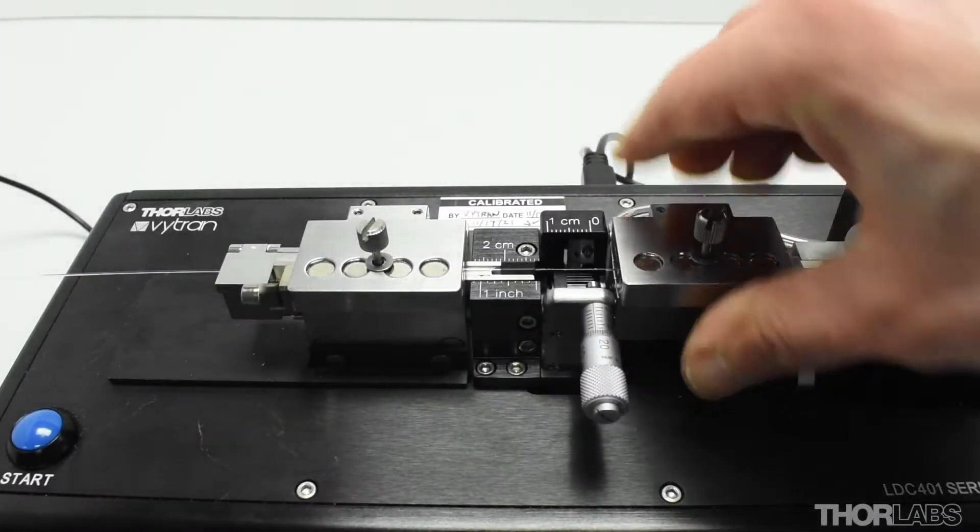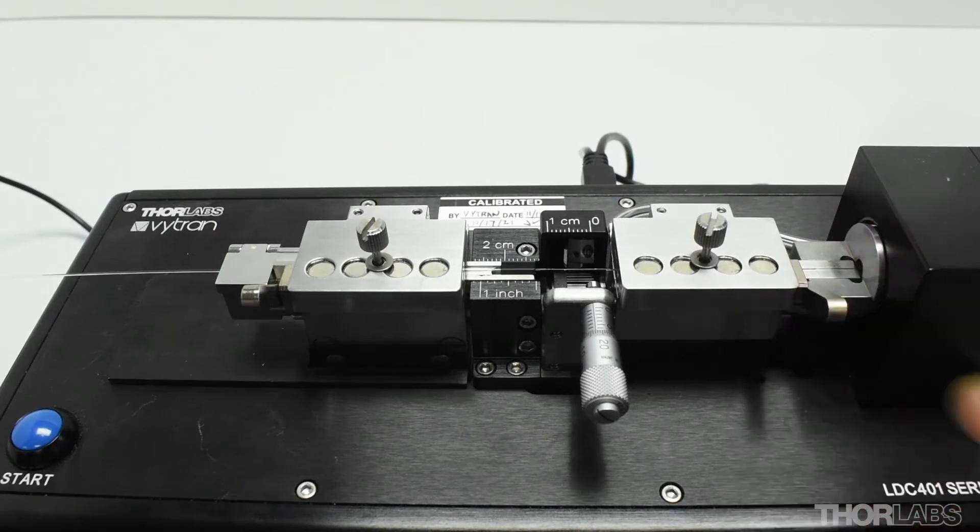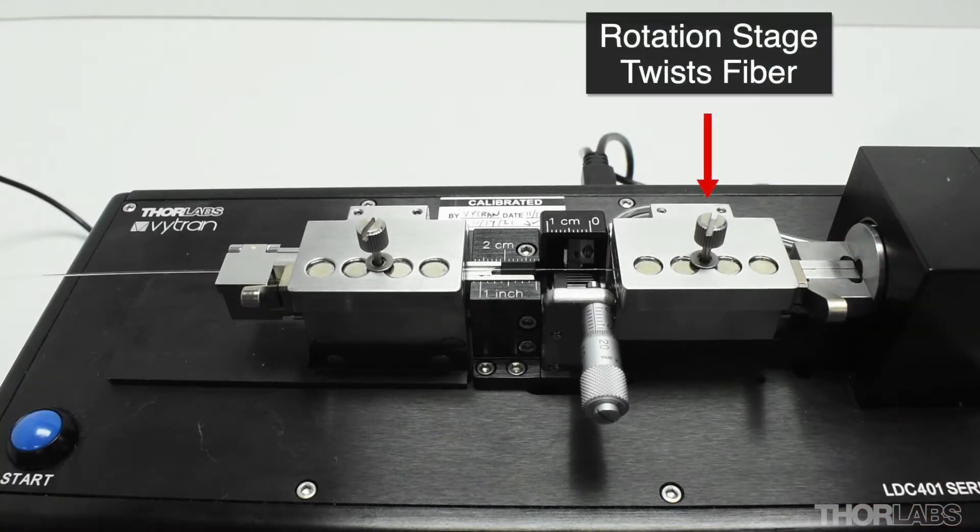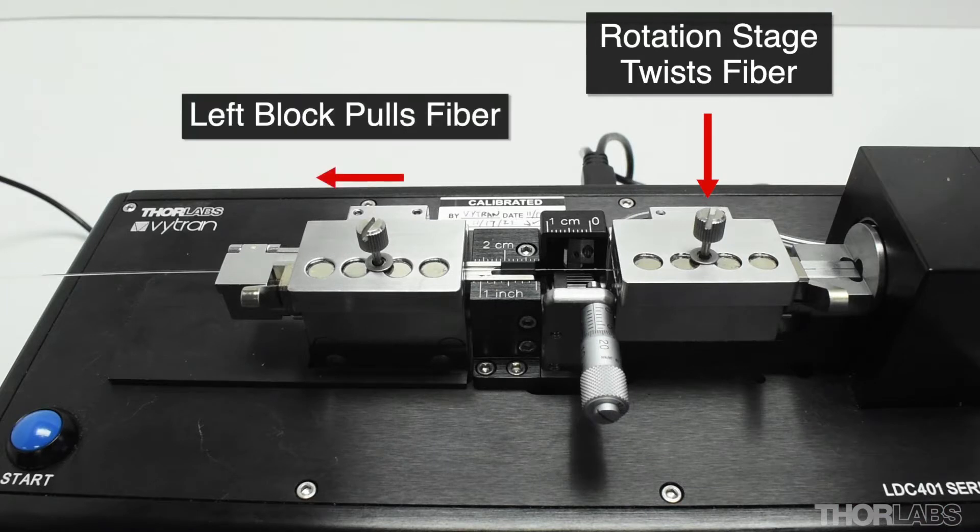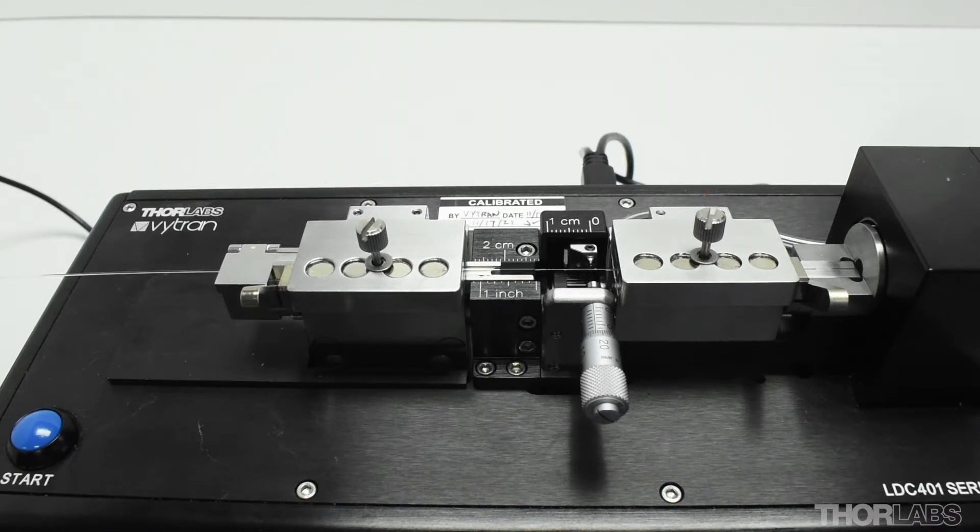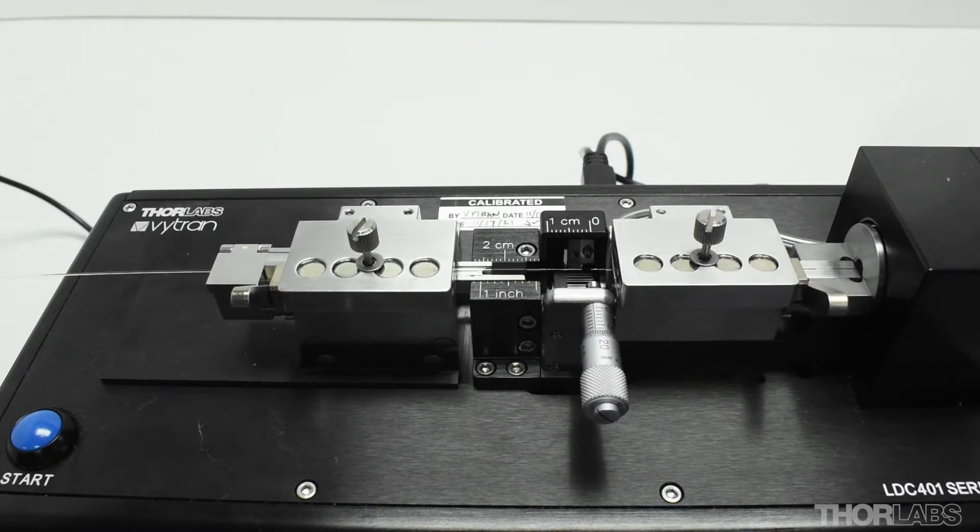The cleavers use a tension and scribe technique. A rotational stage on this cleaver also twists the fiber before it is pulled to the cleave tension. It is this twist that applies torsion to the fiber and produces an angled rather than a flat cleave.